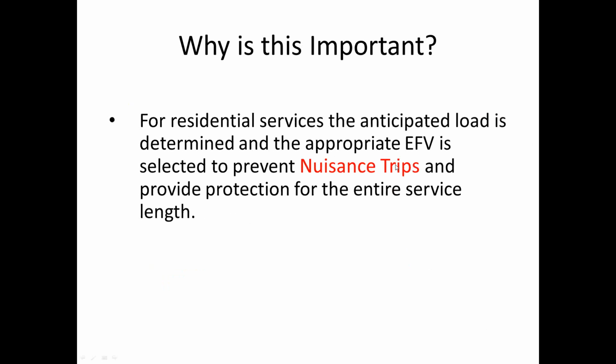So for residential services, the anticipated load is determined and the appropriate EFV is selected to prevent those nuisance trips that you saw, and to provide protection for the entire service length. So you want to do both. And of course you want to keep the minimum pressure at the regulator as well.